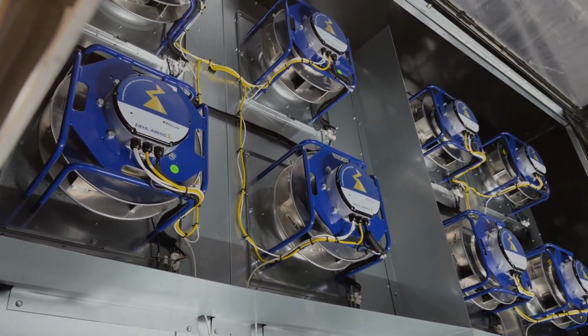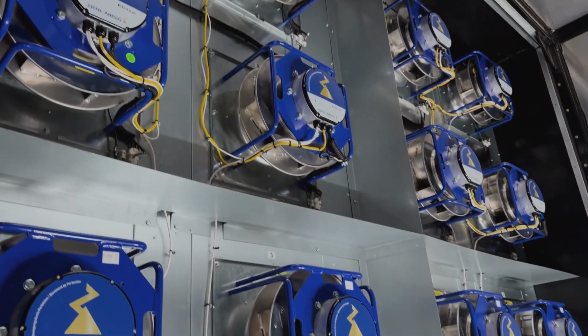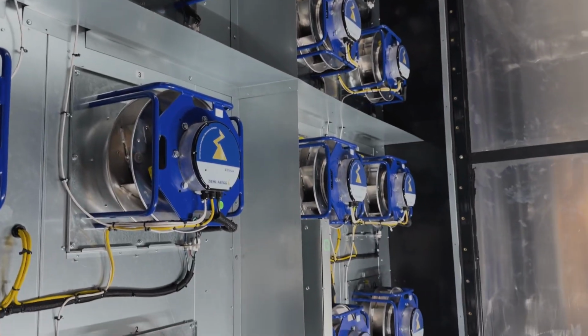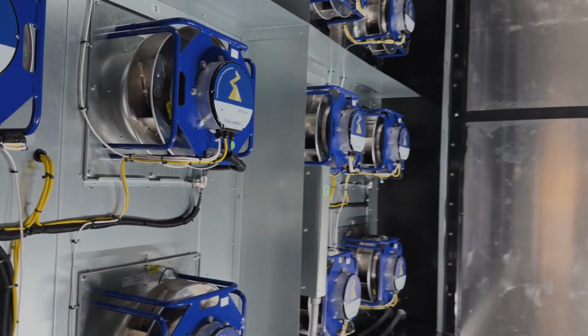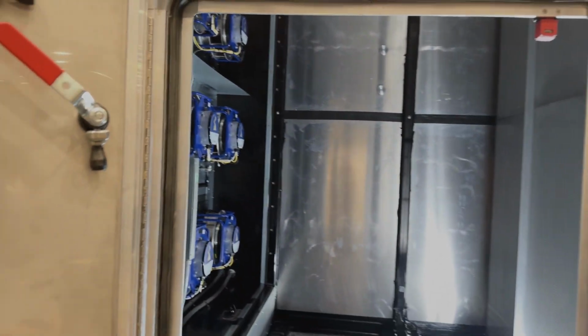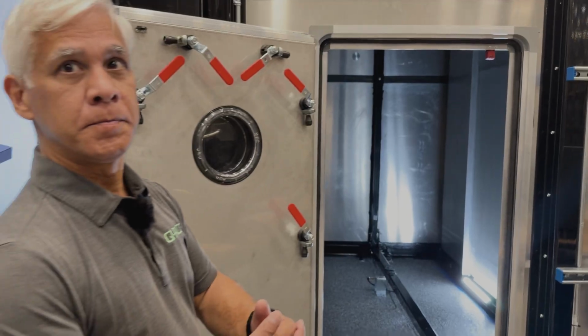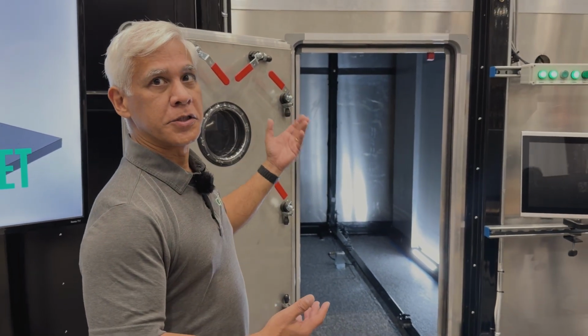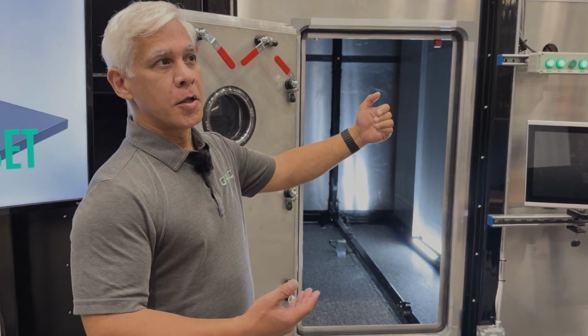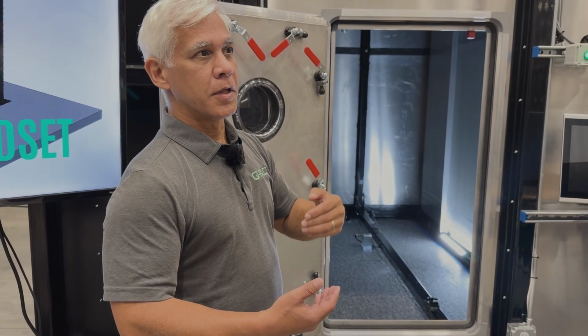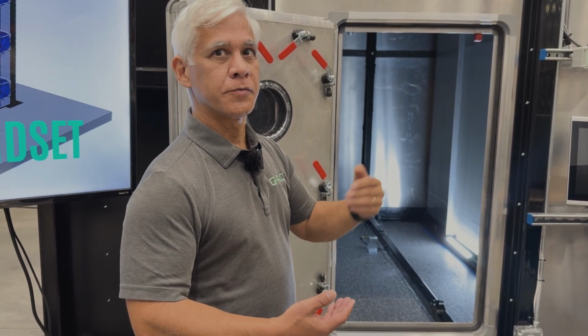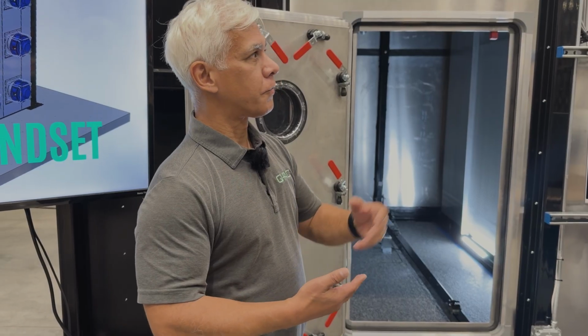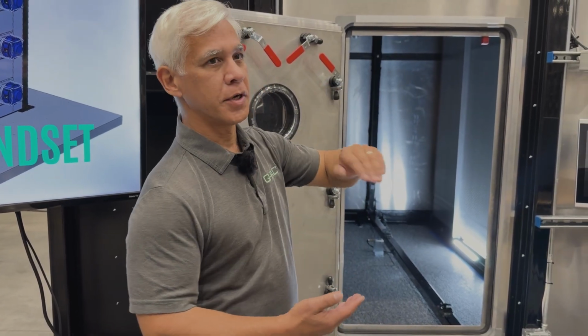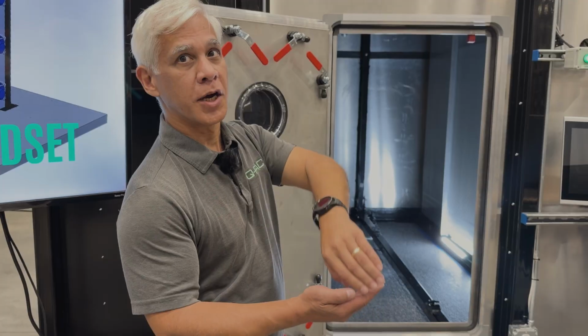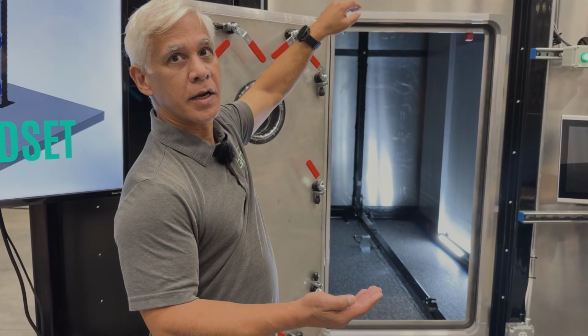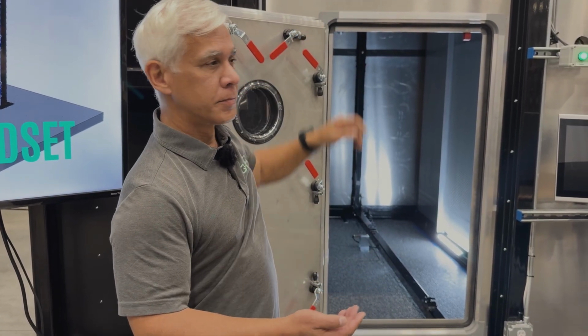One question you might ask is, why do we have fans here at all? Weren't the test fans over on the other end of the tunnel? Well, the answer is, if we didn't have any fans here, if we just had an opening, and we were operating our test fans at a certain speed, that resistance to flow through the tunnel is going to give us a certain pressure. But we need to be able to test the different pressures for the same speed. Because when you walk across the fan curve, if you go from bottom to top, you're going from higher flow and lower pressure to lower flow and higher pressure.